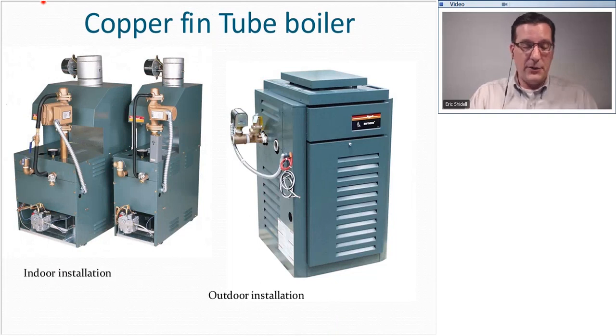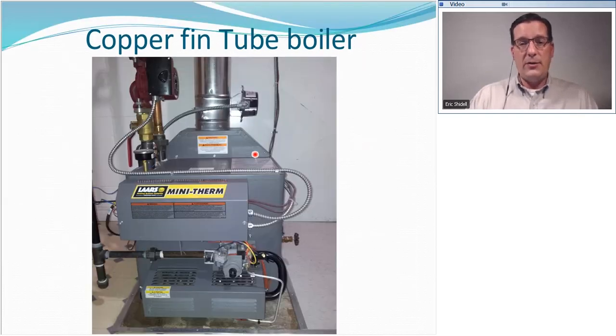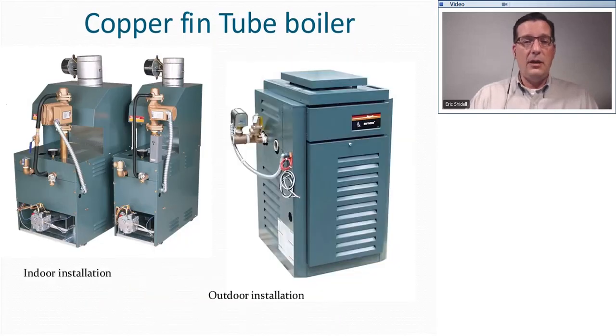They can be for space heating. They can be dedicated for domestic water heating. They can be dedicated for pool heating. They can be located indoors, or they can be located outdoors. A lot of flexibility. Here we have some indoor installation Raypak copper fin tube boilers. These happen to be natural draft gas boilers. Here's the draft hood and the flue on top. On the one in the previous page, the draft diverter is in the back. This one is an outdoor mounted boiler, and it has no flue on it whatsoever. It just vents to the atmosphere.